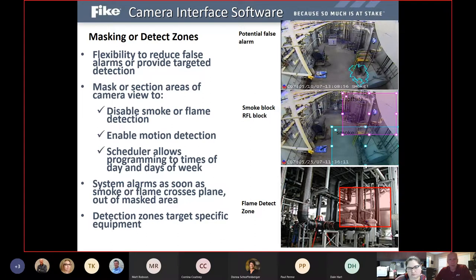And this slide here is just to give an example of how we can program in some of those zones for detection. So very easy to just draw in squares, rectangles, circles, or any kind of shape you want to work in some of your zones or schedules for detecting or ignoring things or different sensitivities. So if we are in some heavily industrial areas where maybe there are some flames that are regularly present, or some steam output from boilers or pieces of machinery, we wouldn't want that to set the camera off every day or shift or however often it happens. So we will program around that, based on what we know happens in the area, to make sure that we go into alarm when there is an actual event, but don't get tricked into a regular occurrence setting the system off.